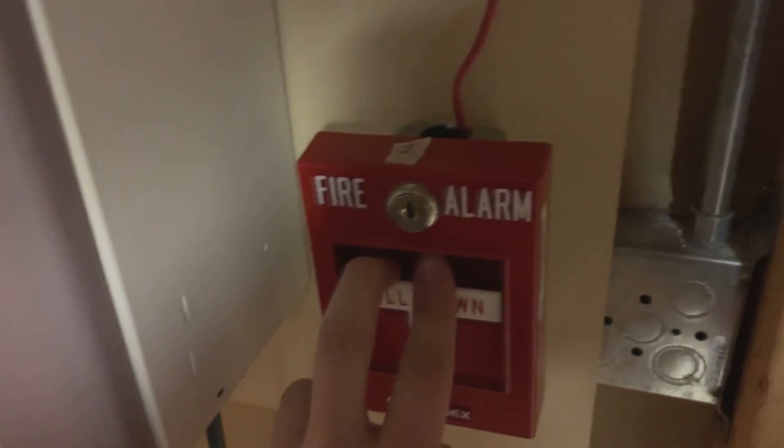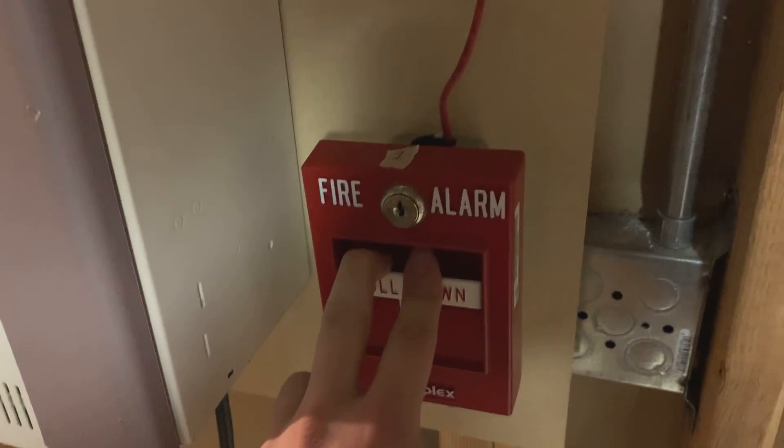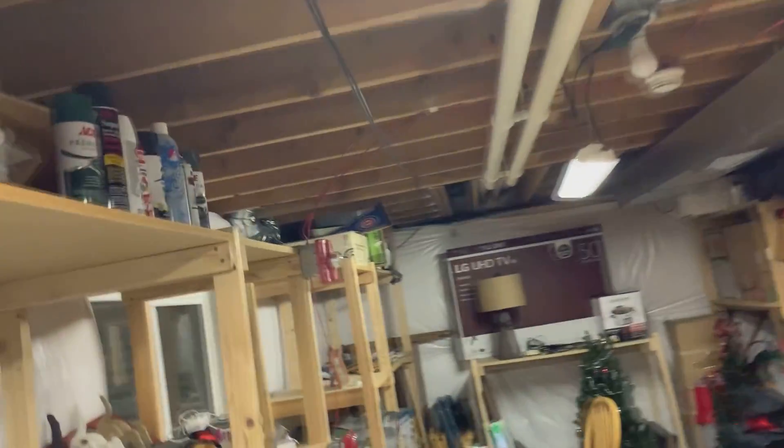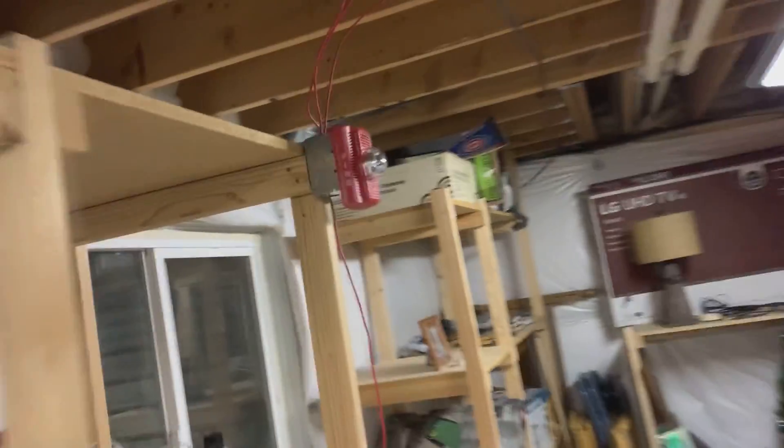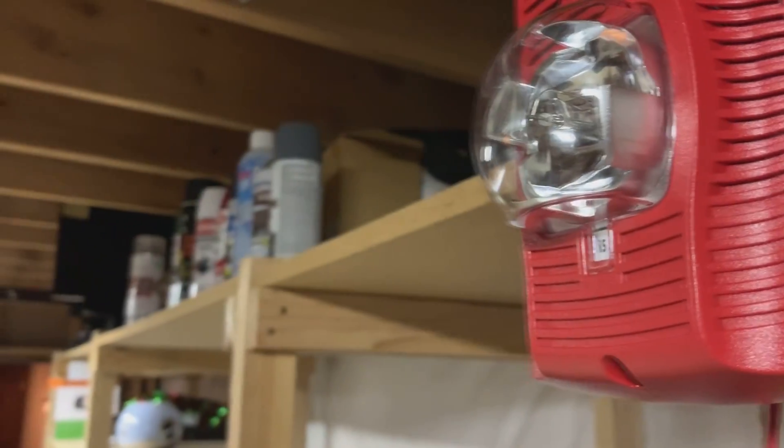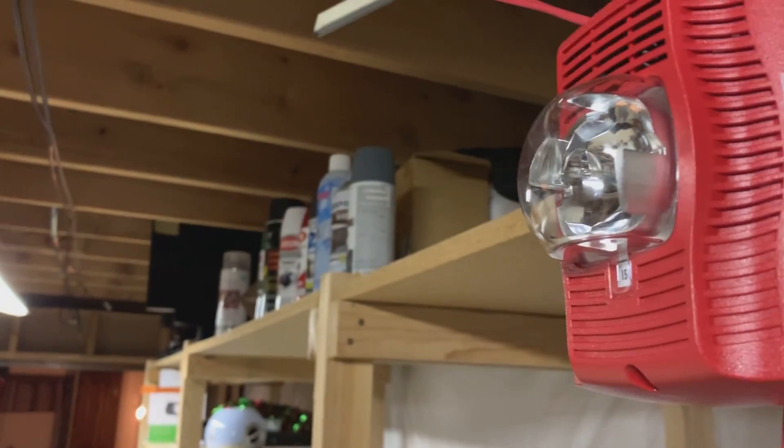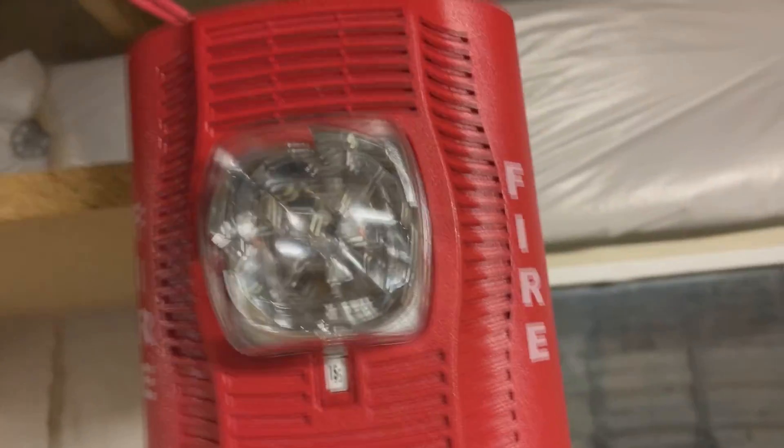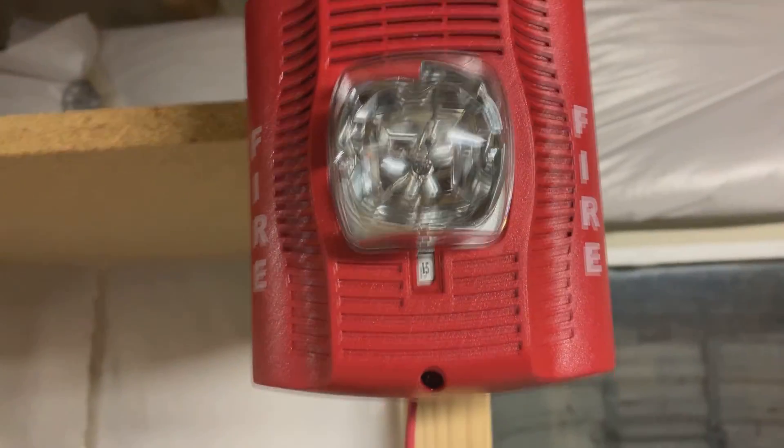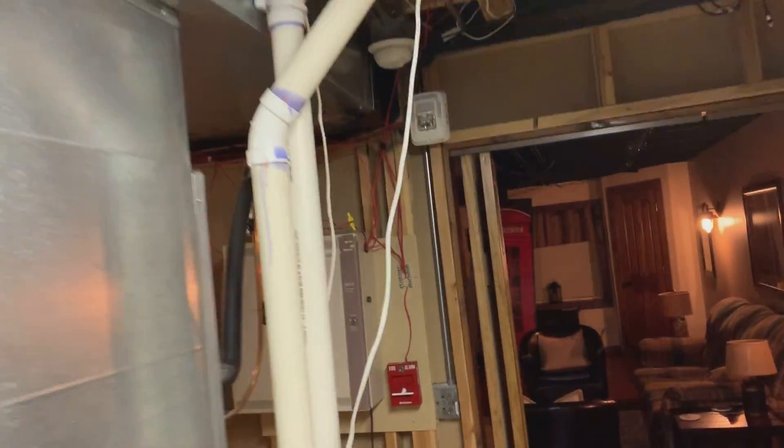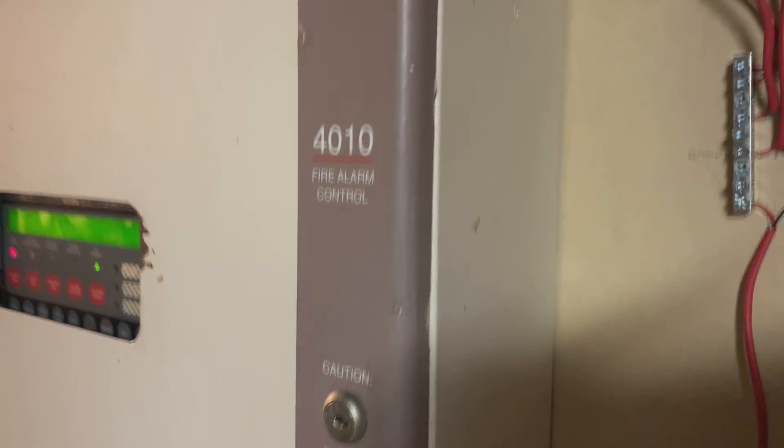A change is made. We're going to try to hit this pull station here and see if we get slow whoop. Attention. Attention. Attention. An emergency situation has been detected in this building. Proceed to the nearest exit and leave the building. Do not re-enter the building until directed to by the proper authorities.